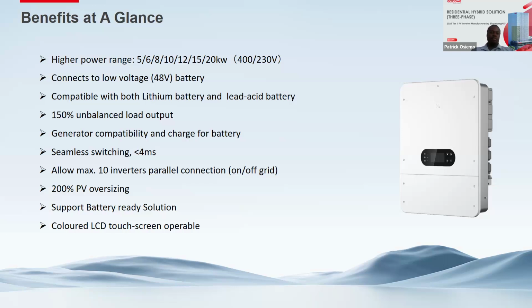ETLV comes with less than 4 milliseconds switching, so your appliances won't even sense that there's a blackout from the grid side. And if you have a home that keeps on growing in terms of electrical appliances, that is not an issue, because with the ETLV you can scale up your system from a single inverter all the way to 10 inverters installed in a single system, working as one, whether it's hybrid or completely off-grid.